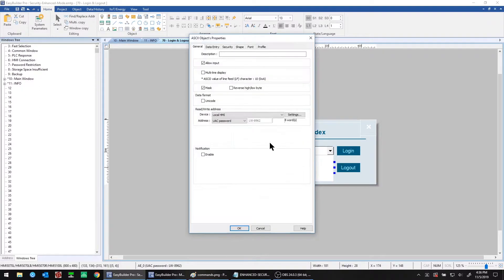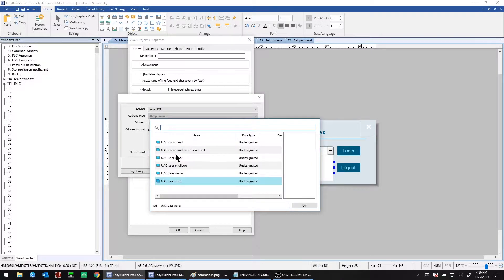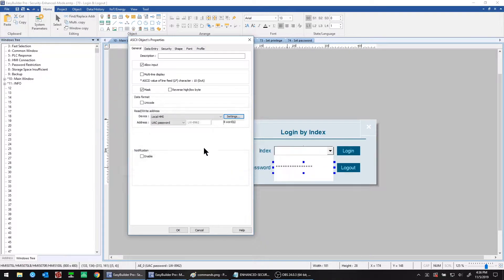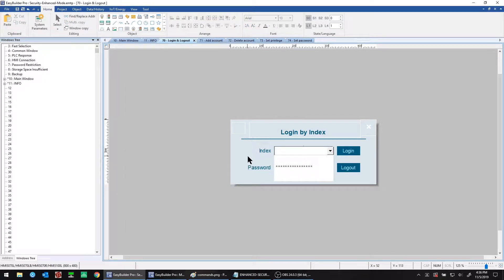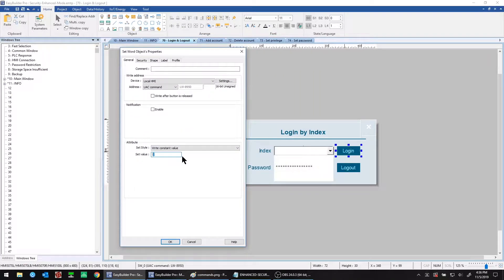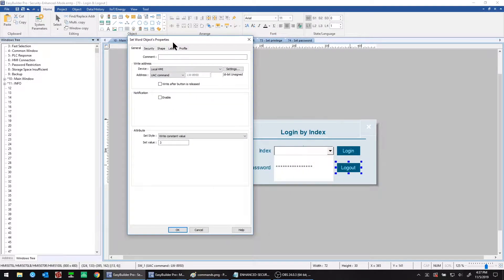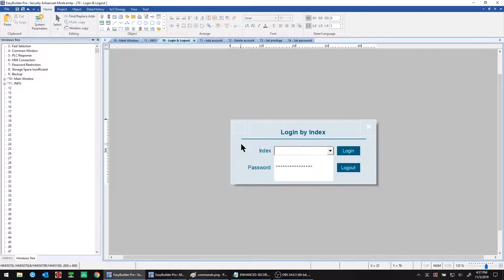Next is a password entry, so we use an ASCII object for this. UAC password is the name of the tag — it is 8 words long. You can find it easily from the address type drop-down field in settings. Once an operator has entered their selection and password, they can use a set word object writing a value of 2 into the UAC command or control register to log in the designated user. A logout button can be created with a set word object as well, writing a value of 3 into the UAC command register.